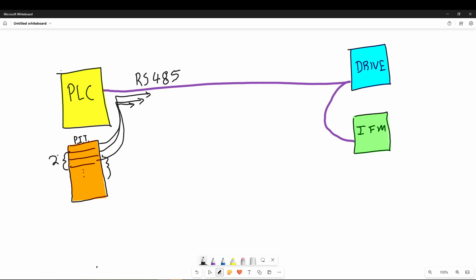This leads to a situation where the first bytes of data don't match the data that is in the last parts of the packet because the PLC updated in the middle of the transmission. This data is now considered inconsistent because the data represents two snapshots in time. For a lot of applications, this might not be a problem, but for some, it could be disastrous.